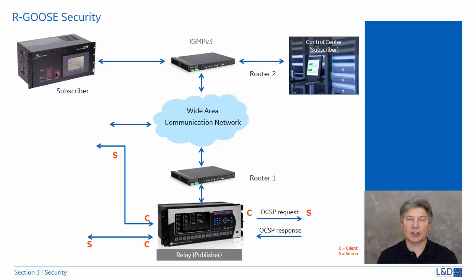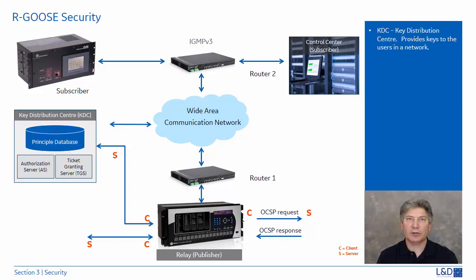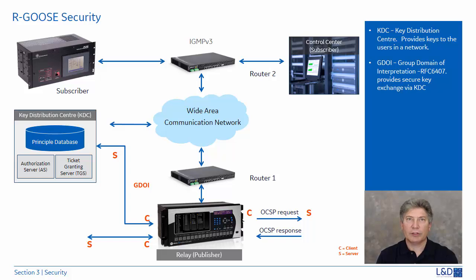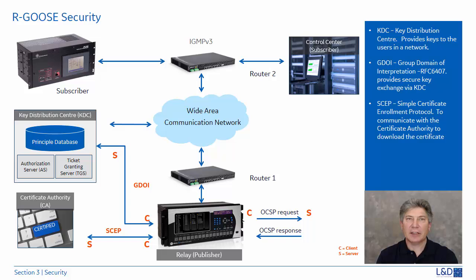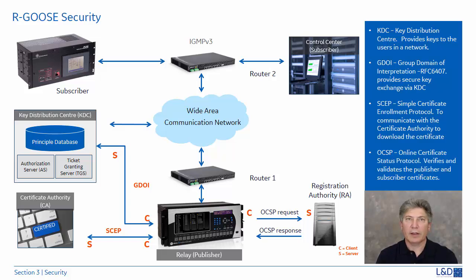In this section, we will review all the components used in a secure routable message configuration. First, we have a Key Distribution Center, or KDC — a system responsible for providing keys to users in a network that shares sensitive or private data. Each time a connection is established between two devices, they both request the KDC to generate a unique password for verification. The protocol used to access the KDC is known as GDOI, the Group Domain of Interpretation, which provides a secure key exchange between the KDC and the devices. SCEP, the Simple Certificate Enrollment Protocol, is used to communicate with the certificate authority responsible for issuing and managing certificates. Finally, OCSP, the Online Certificate Status Protocol, is used to communicate with the registration authority to verify and validate the publisher and subscriber certificates.